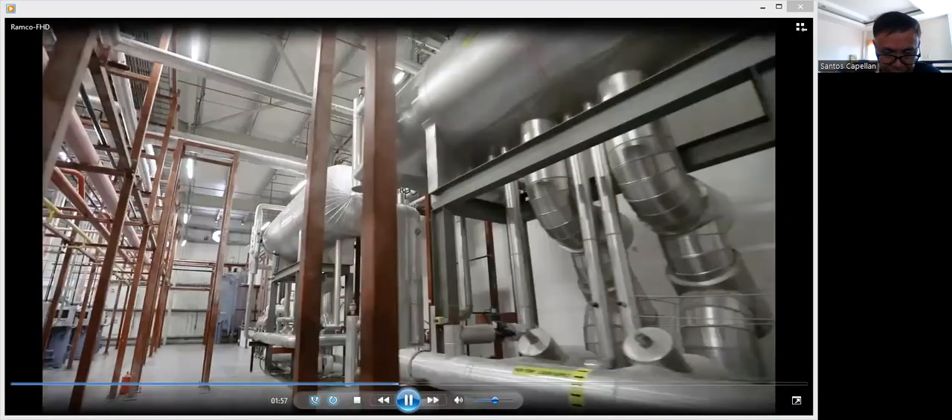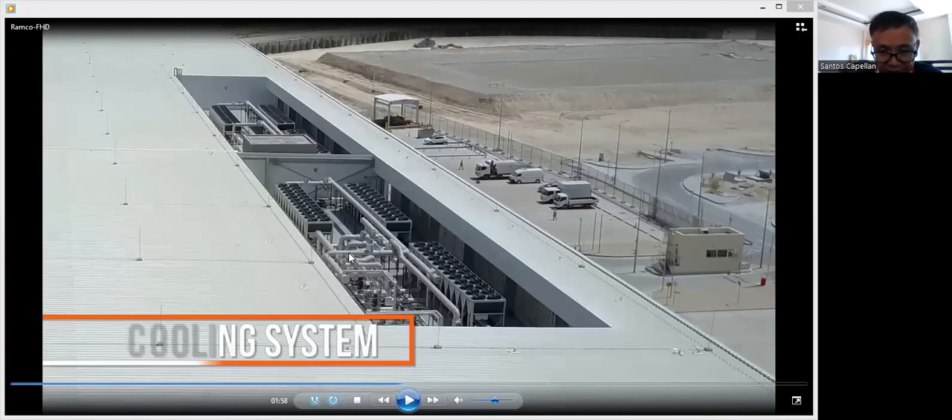This is the refrigeration plant — we used SCADA here. Now these are the chillers for B3 and B4. These chillers provide cooling in B3 and B4. The cold room temperatures are controlled in the refrigeration plant, but in B3 and B4 the temperature is controlled by these chillers. These are air-cooled chillers. The system we used for the chiller plant manager is Trane, and from the Trane system I tried to software-integrate it with our building management system, Schneider.